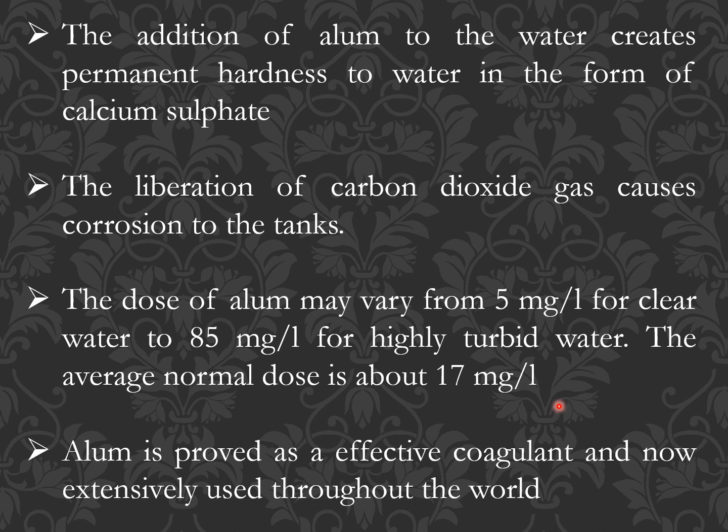They are allowed to flocculate, the flock is created, and it makes the colloidal particles settle down. A normal average dosage is given, but every day in a water treatment plant the alum dosage is decided by a jar test only. Normally it is decided based on the turbidity of the water.